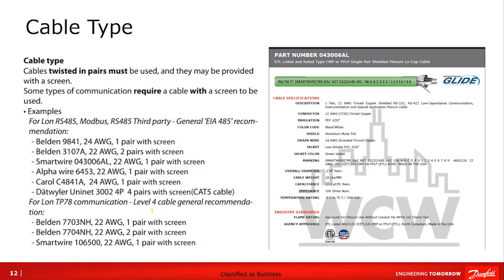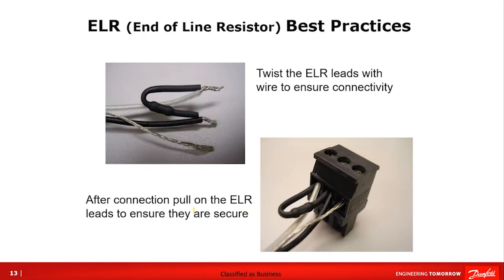TP78 uses a level four cable — not necessarily the same cable type as other comm types. For TP78, level four cable is our recommendation and the spec for the devices. For end-of-line resistors, they go across the A and B wires on the connection point — typically 120 ohms. I like to see them twisted in with the comm leads, because if not, they can potentially vibrate or have a loose connection, which may cause the same communication issues.